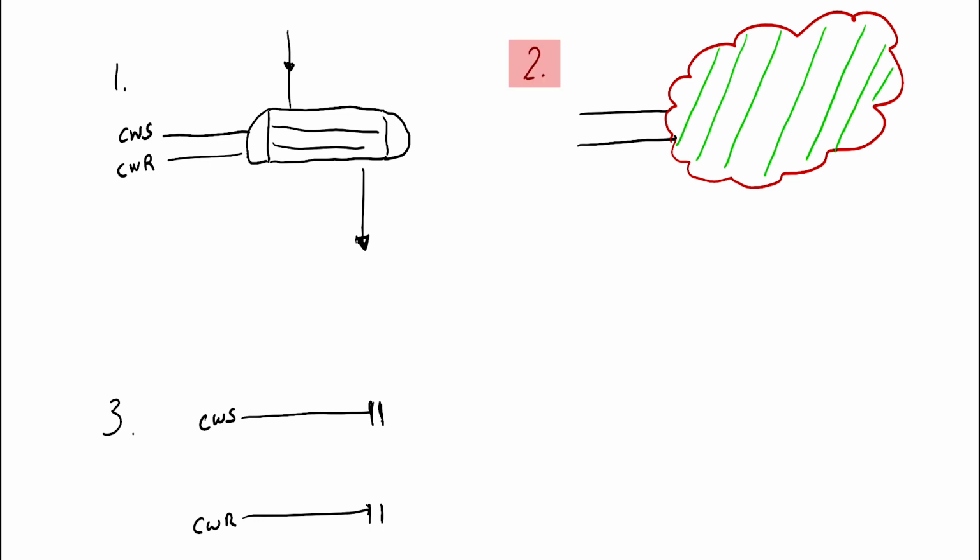So in number two, in the revisions in the MOC revisions of this drawing, we need to cloud that area. That red cloud is going to stay. It's going to signify that there was something here that we took out. Those green lines there are dictating that we are going to take something out. So you would draw the red with the green over on top of the exchanger on the demo drawings, and on the live drawings version of the MOC, it would have the cloud stay. Okay, so then in the new versions, when it comes back into the system, the next revision, you can remove the clouds from the drawing.